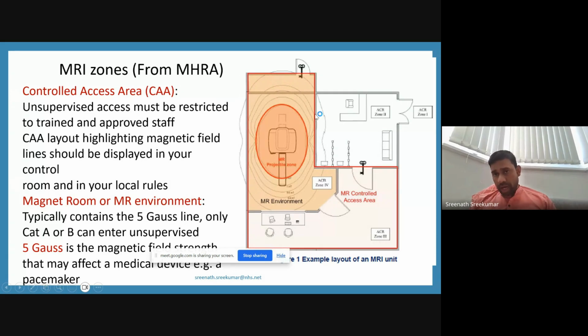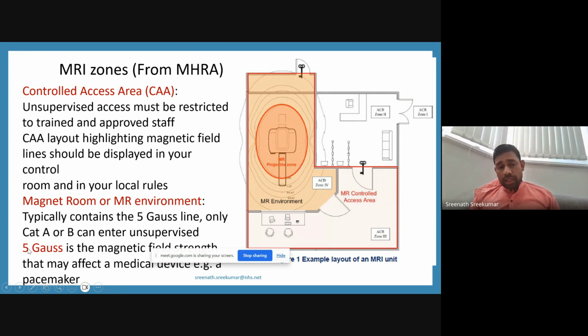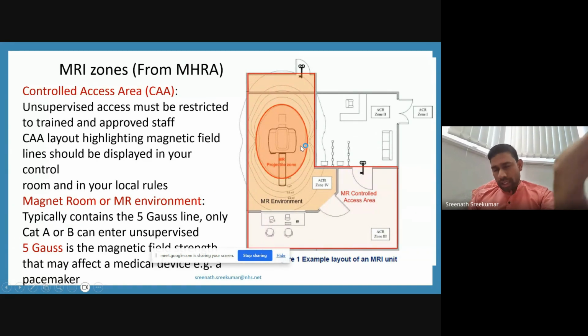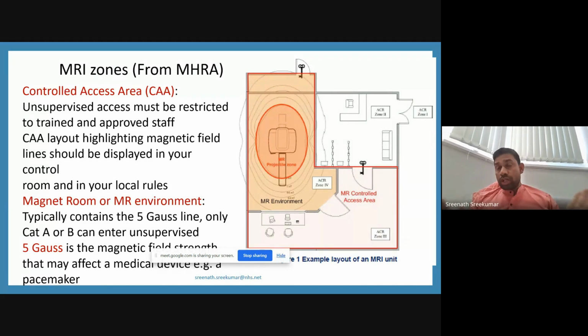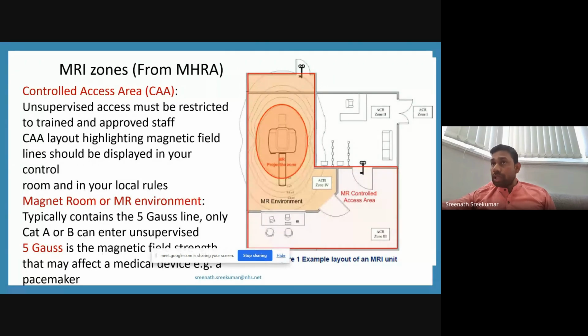outside the controlled access area. We have the MR environment and the projectile zone. Also, we can demonstrate it there. There is another term, the 5 gauss line, or 0.5 millitesla line in the new version of the documents, which says that the MR strong magnetic field can extend at least 0.5 millitesla, or 5 gauss, outside. Only some of the active devices are allowed to go inside without any checking. So the 5 gauss line is a very important line in the controlled access area or MR environment.